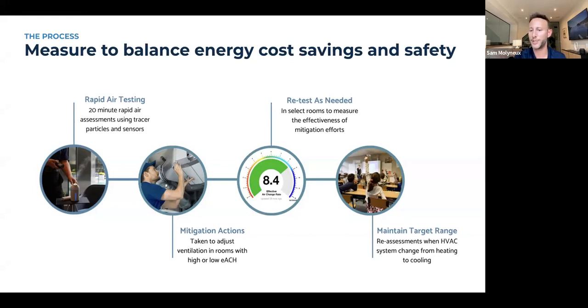And with the ACH in hand, which can be measured in about 20 minutes or so, we have the benchmark for that room, the reference number for that room, and then we can understand where we are in that Goldilocks zone. Are we above 6 ACH? Are we below 6 ACH?